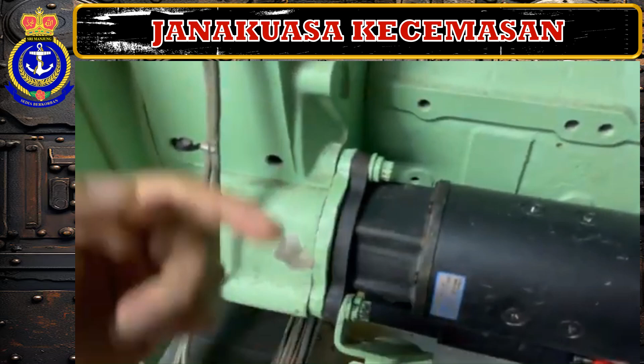Once the moment comes, this energized voltage will draw back, and this gear will come back to its position, and therefore the flywheel will take over. And once the flywheel takes over and minimum firing RPM comes, the emergency generator will fire. This is a turbocharged Cummins engine.